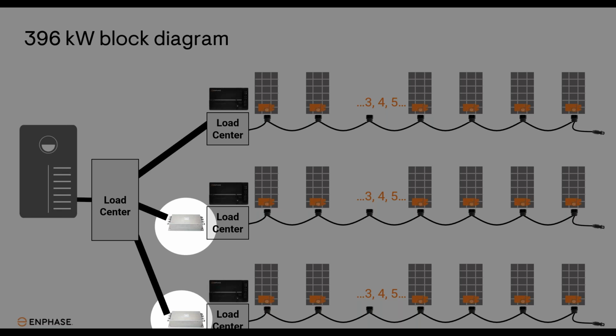And also, even if you have one commercial gateway, or you have less than 276 microinverters, you still might have to install a line filter if you're on a building that has a lot of line noise coming from machines, medical equipment, different things like that. So it's always something to keep in the back of your mind when you're designing projects: what is inside of that building, what is using that power inside of that building, so you understand if a line filter might be needed for that clean communication.